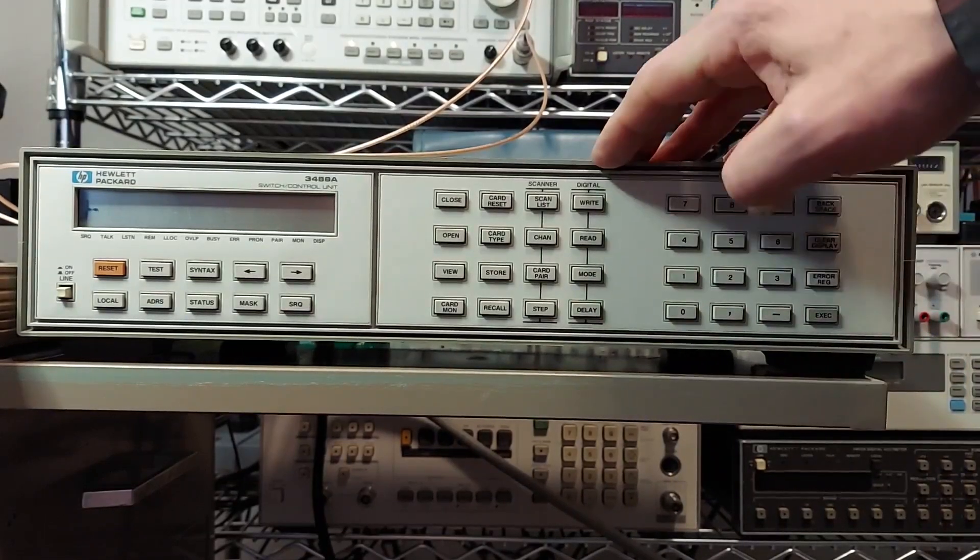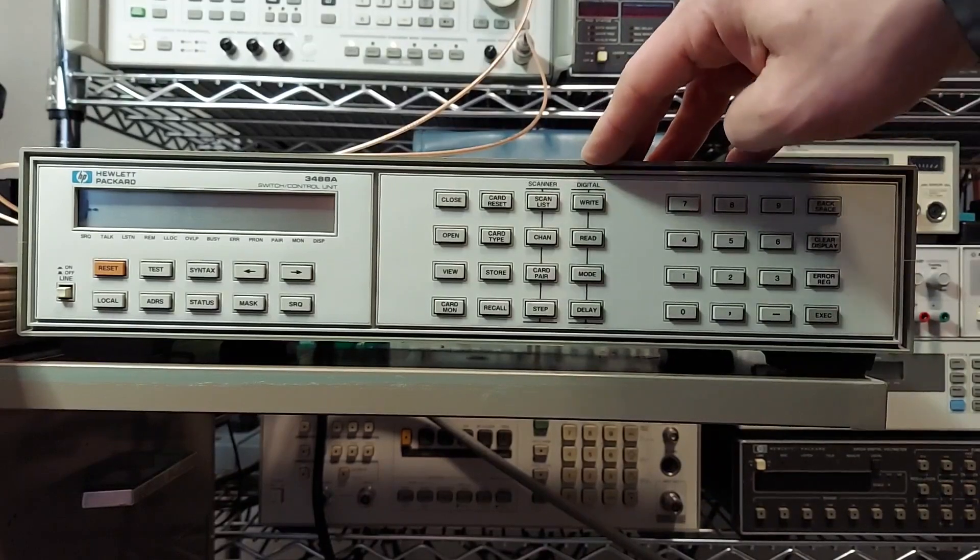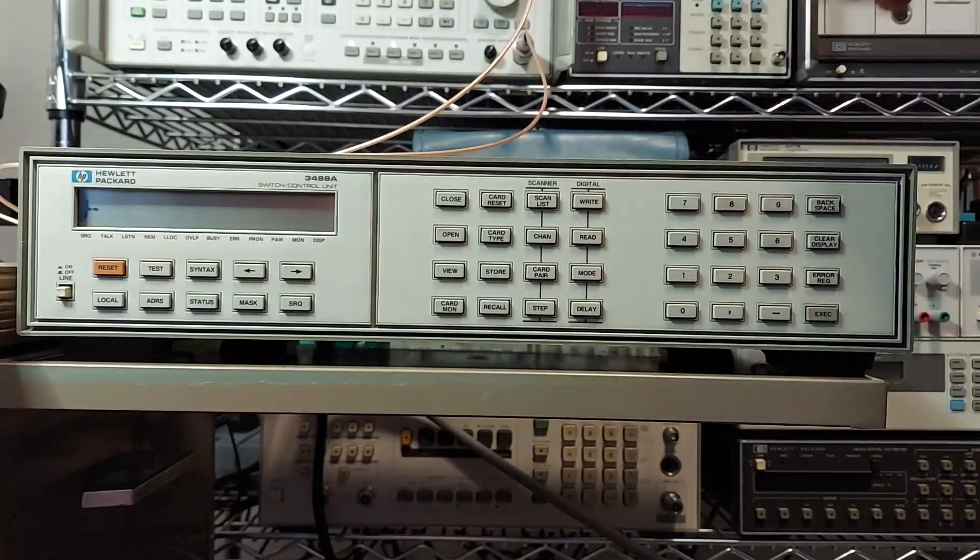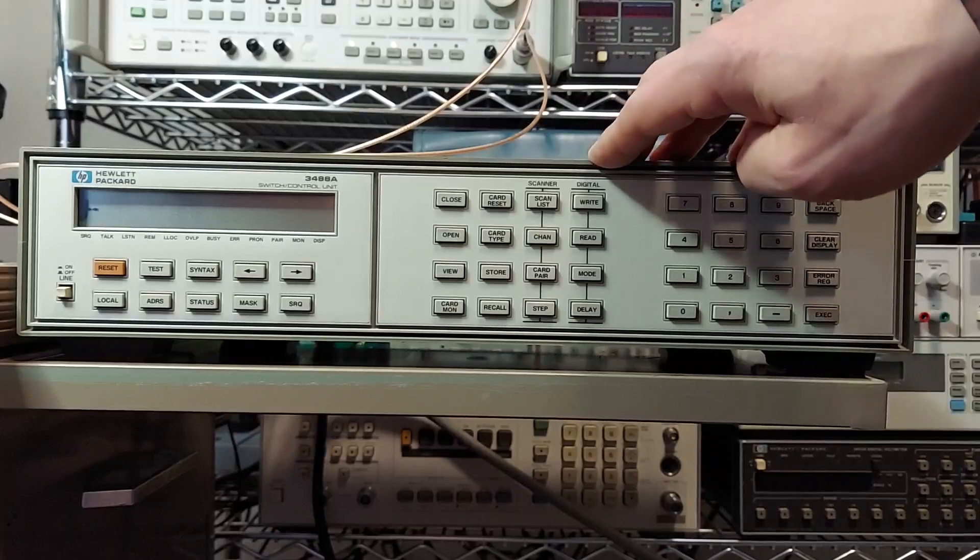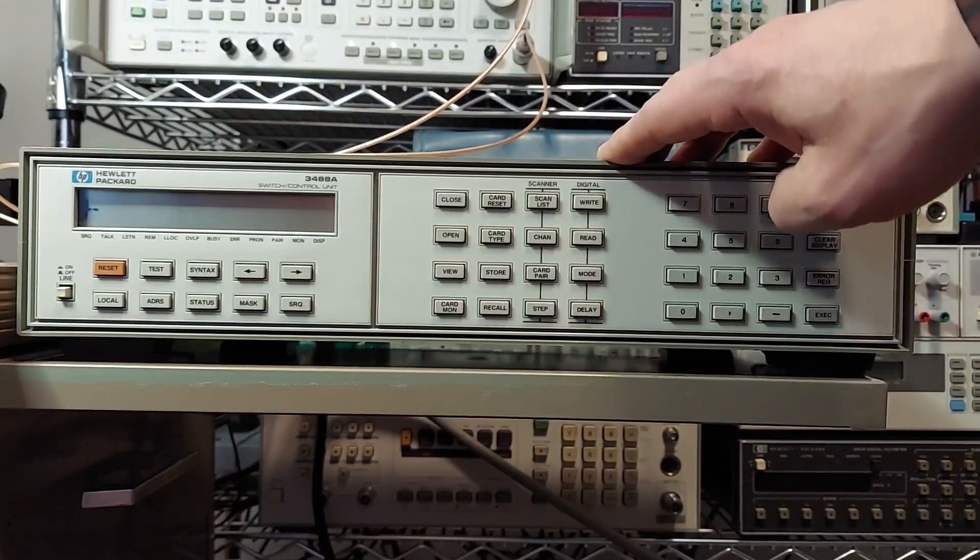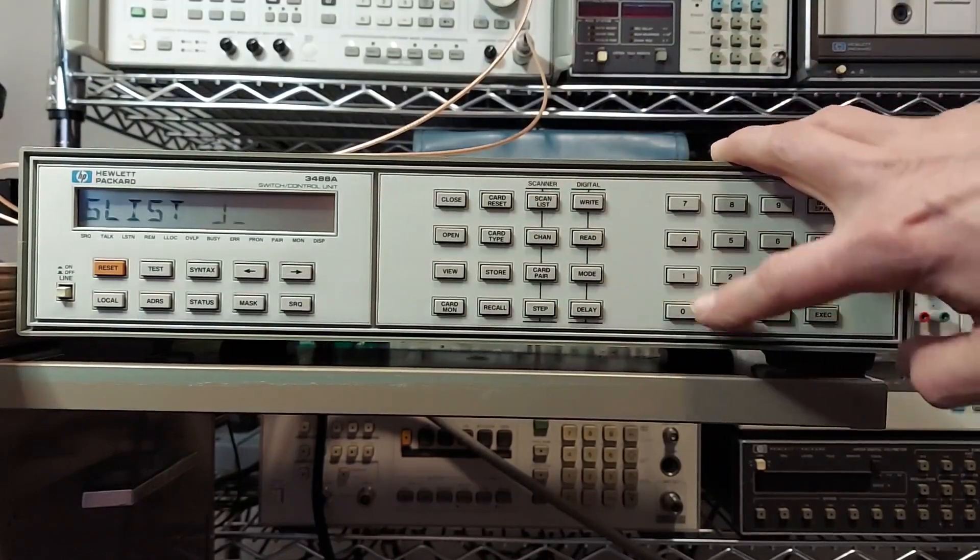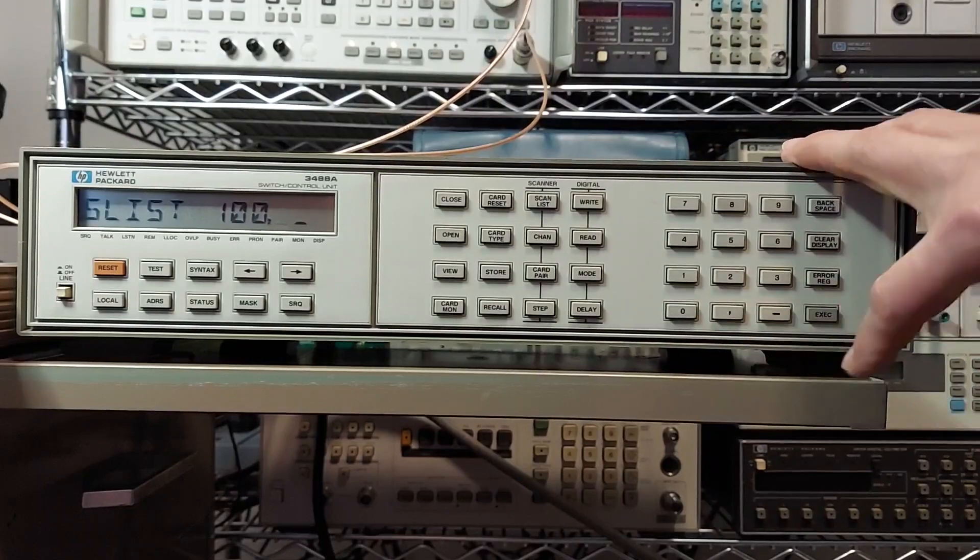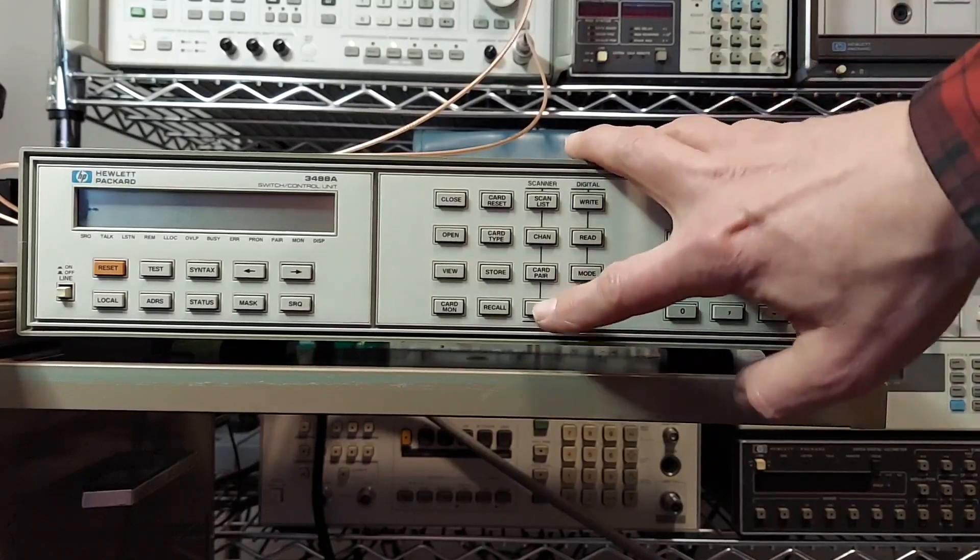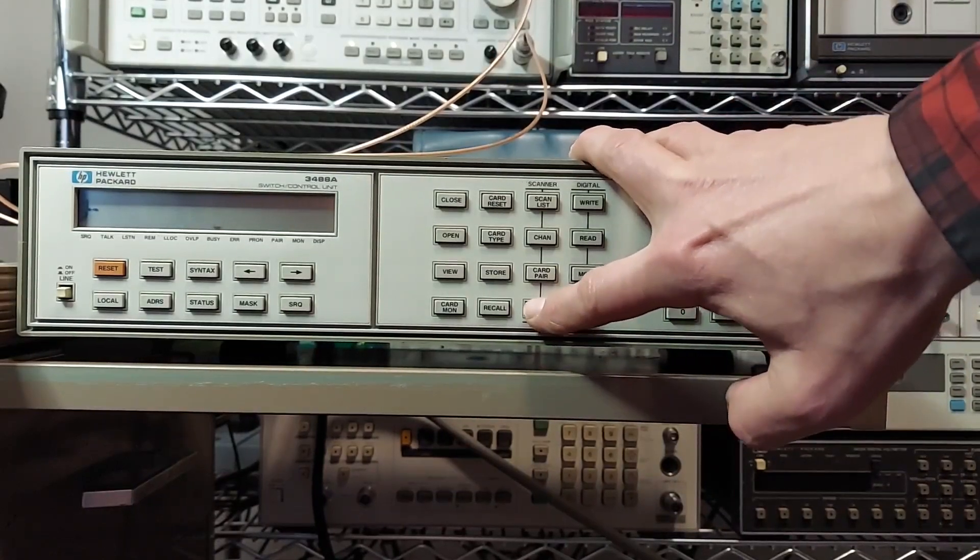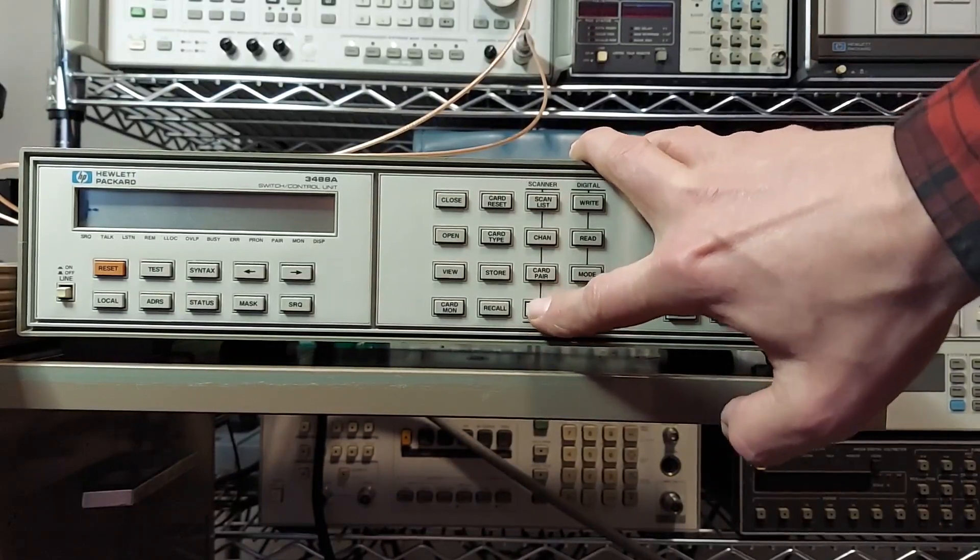I can also set up what is called a scan list, where I can instruct the instrument to step through different ports on the back just by setting up a list. So say I've got two ports used right now. I can set up a scan list, and it's going to be card one port 00 and card one port one. Enter that. And then I can press the step button and step back and forth between those two ports.